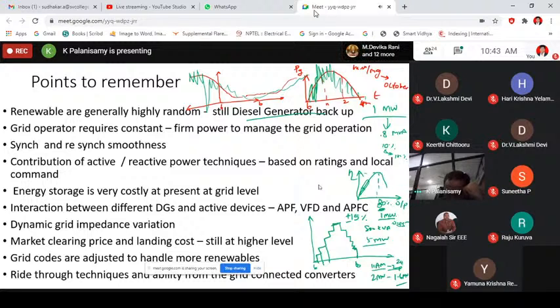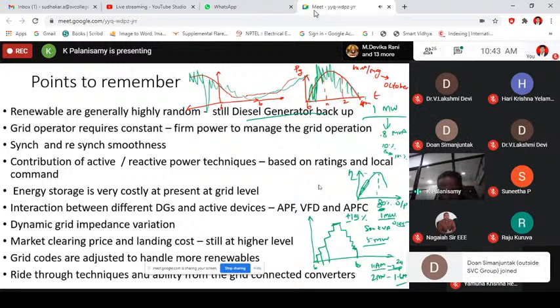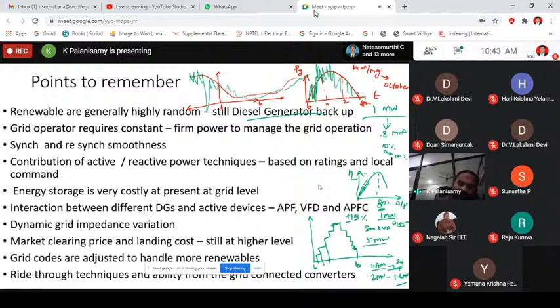I repeat, let us say it's a rectangular area of power distribution. I'm measuring the voltages from all the 4 corners, right? And in one particular interval, the northeast measurement is giving, as I told you, plus or minus 5% voltage variation, which is okay, but the phase angle, when compared to the other 3 corners, is alarmingly high, it is deviating much. So I must understand there is going to be some issue close to the northeast corner.